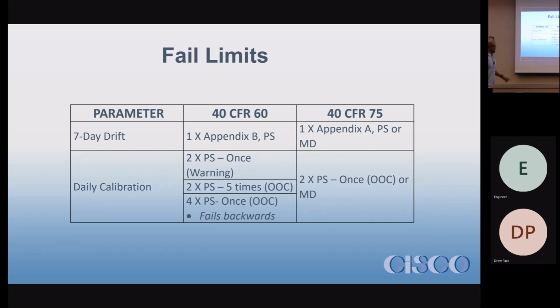Part 60 adds that nice little caveat, or I'm sorry, if you go back to the higher one, if you fail 2 times the performance spec once, I think we acknowledge it as a warning, correct? It's simply a warning. We used to call it a fail, so it would excite someone to take action to fix the issue. But people started to worry, is our data invalid? They were over panicking, so we changed the wording so that it says warning now. But if you fail that 2 times, 5 times in a row, it becomes out of control. The 4 times, as I mentioned yesterday in my presentation, that's the big one because it invalidates backwards to the last passing calibration. And once again, I'll just remind you, you don't want to have a valuable test in between those 2 calibrations, or especially if your source test has left the building, then you've invited a whole additional set of problems.